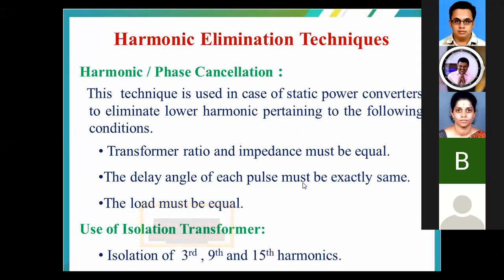And the last one is the use of isolation transformer. Here, with the aid of the isolation transformer, we are able to eliminate the third order, ninth order, and the 15th order harmonics specifically.